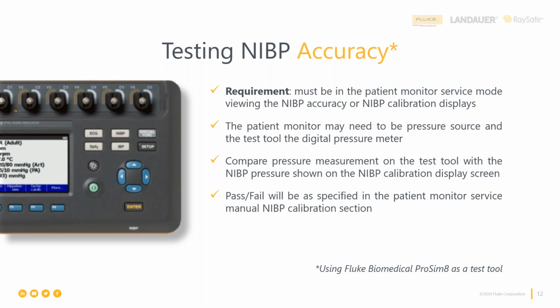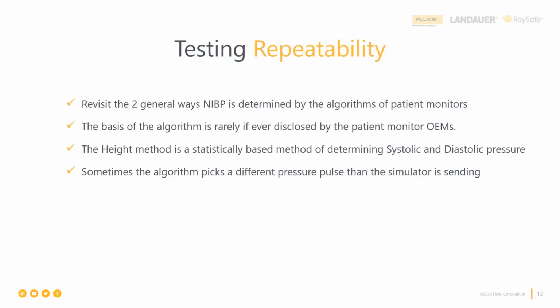And if it fails, then we do a corrective action to figure out why. Is there an adjustment we can make to bring it into tolerance, or does it need to be repaired or replaced? Okay, so that's how we're going to assess the accuracy and what we're going to do with it. And it's really, really important. Repeatability is what we can use the dynamic simulation for.